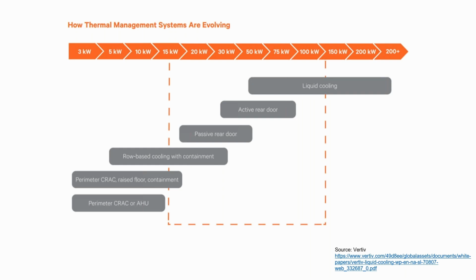And then we shift towards we need some help from liquid cooling. So we talk about passive and active rear door heat exchangers. Those are the type where we have a liquid cooling coil right on the back of the rack, and we're running cool water through there. And the passive versions, there's no fan assist on that. We're just allowing natural convection to pull the heat out of the servers. The active ones have an array of fans on there, and obviously, as you can see here, pull out more heat. That's considered sort of a hybrid cooling because we're not bringing the liquid directly to the chip. We're just creating the heat exchange a whole heck of a lot closer to the chips than we were before. And then you get on to legitimate liquid cooling, and then we're talking about direct-to-chip cooling or immersive cooling.